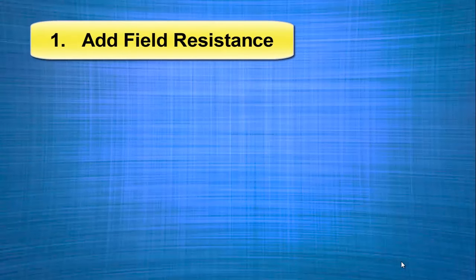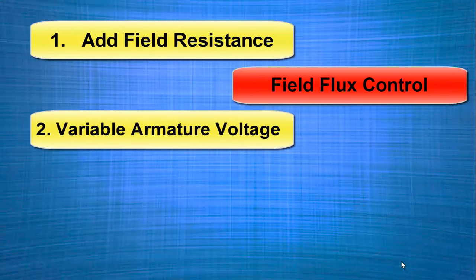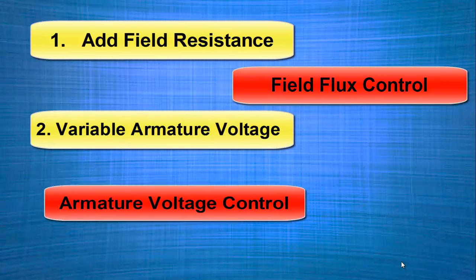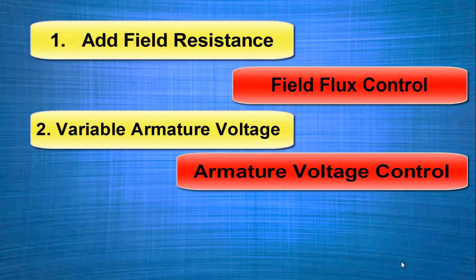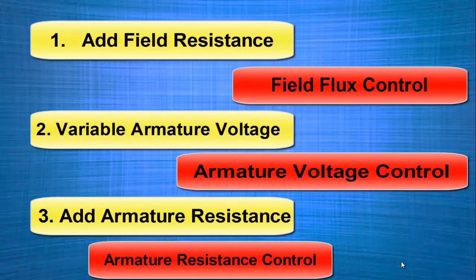The first method is by adding resistance in series with the field winding. This method is called field flux control. The second method is variation of armature voltage using PWM or Ward-Leonard method — this is called armature voltage control. The last method is adding resistance in series with the armature circuit, called armature resistance control.